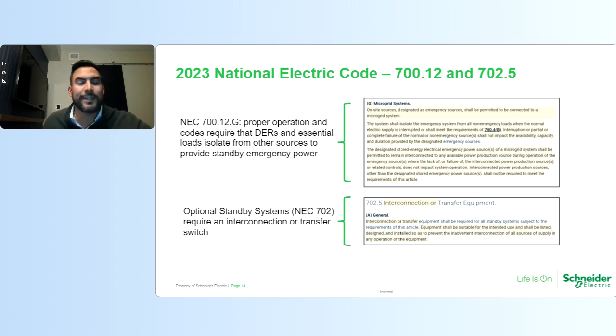Now, why is that important? If you think of your battery energy storage system connected to your main switchboard, which has essential and non-essential loads all connected to one piece of equipment, and you open the utility main breaker and have your energy storage system provide emergency power, that entire main switchboard is going to get emergency power. And if you want to shunt your breakers within that main switchboard, now you're modifying breakers.